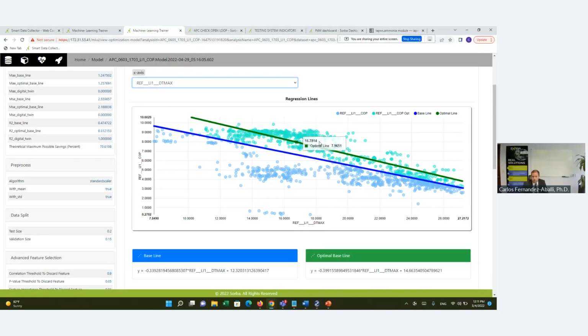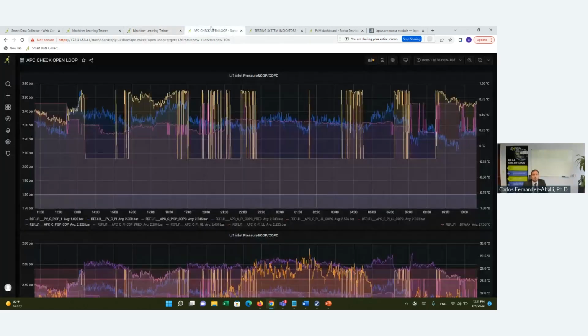Here's another optimization heuristic of a different refrigerator. Okay, this time showing a more modest efficiency gain. And here's again our open loop. And this jumping that you're seeing is created by the maximum high limit and minimum low limit. And that is an important concept, because you say, well, how do you keep control? How do you know we won't have a wacko prediction that is going to give a wacko set point and break my system?